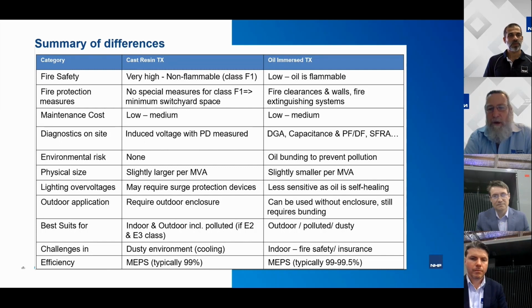Interesting that the standard also allows people to specify a higher efficiency as opposed to the minimum. But the reality is that you don't often see it being specified. Part of the reason is that as you try to make transformers more and more efficient, it's the law of diminishing returns. So yes, you can go to domain refined steels and lower loss steels, and you can do all sorts of things, but at the end of the day, you're trying to crib 0.1, 0.2% to go from minimum to a higher efficiency. And with that, the cost of the transformer goes up. So, interesting debate. All right, that sums up the difference between the two.